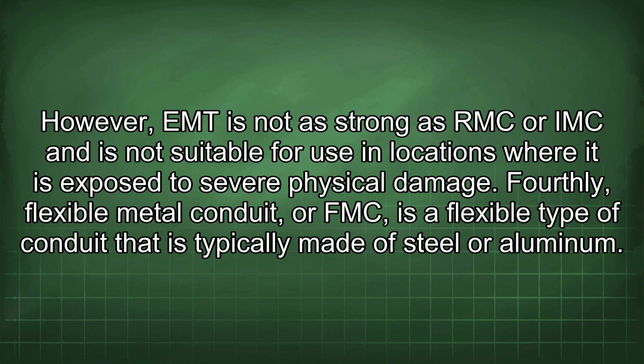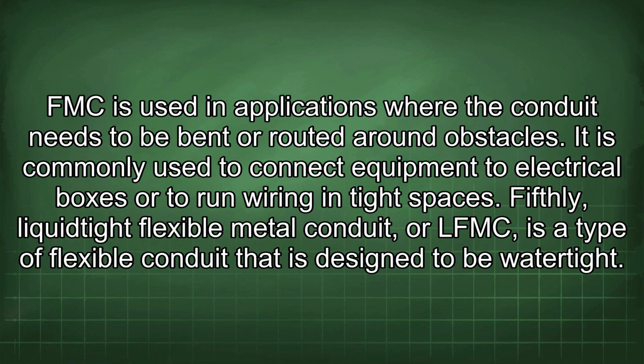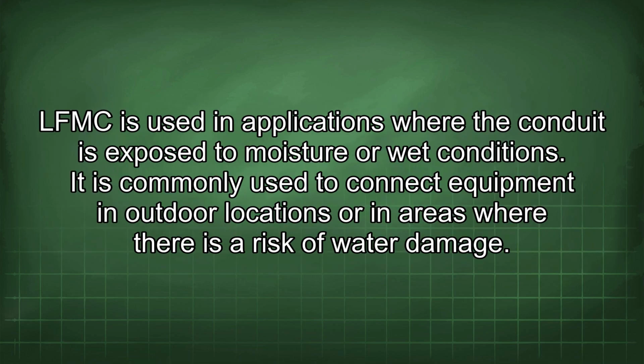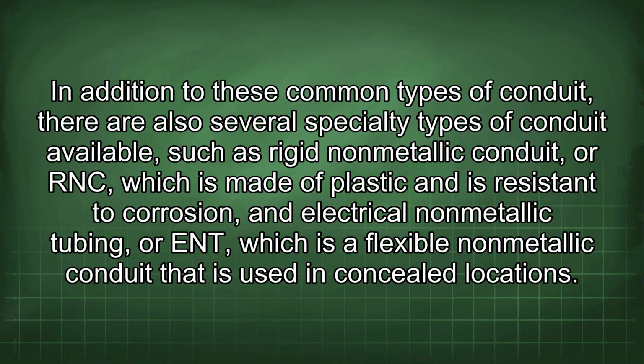Fourthly, flexible metal conduit, or FMC, is a flexible type of conduit that is typically made of steel or aluminum. FMC is used in applications where the conduit needs to be bent or routed around obstacles. It is commonly used to connect equipment to electrical boxes or to run wiring in tight spaces. Fifthly, liquid-tight flexible metal conduit, or LFMC, is a type of flexible conduit that is designed to be watertight. LFMC is used in applications where the conduit is exposed to moisture or wet conditions. It is commonly used to connect equipment in outdoor locations or in areas where there is a risk of water damage. In addition to these common types of conduit, there are also several specialty types of conduit available, such as rigid non-metallic conduit, or RNC, which is made of plastic and is resistant to corrosion, and electrical non-metallic tubing, or ENT, which is a flexible non-metallic conduit that is used in concealed locations.